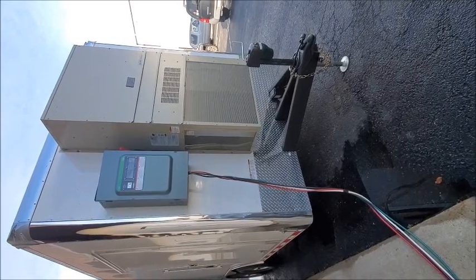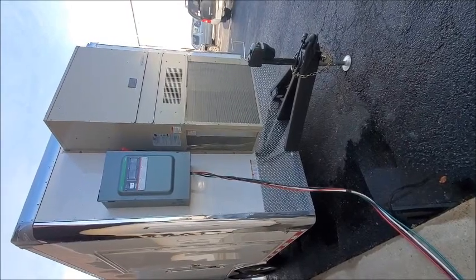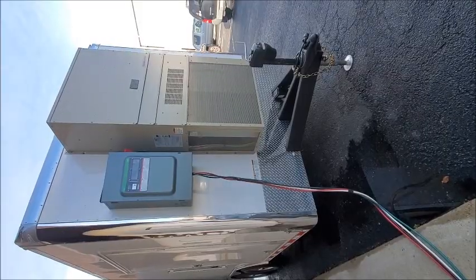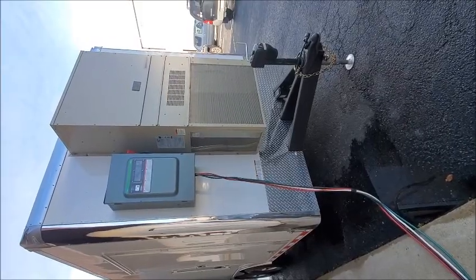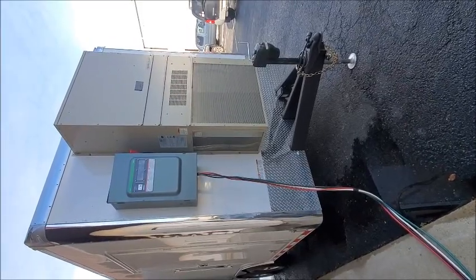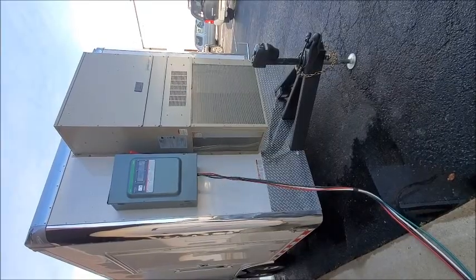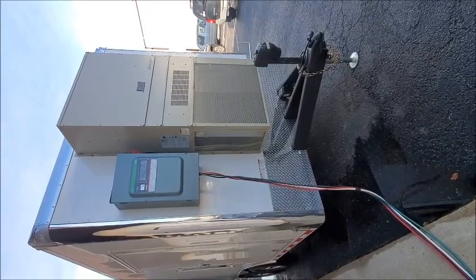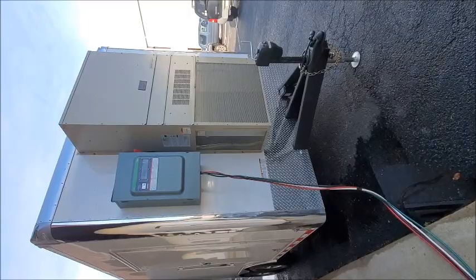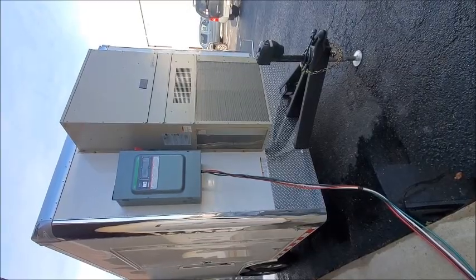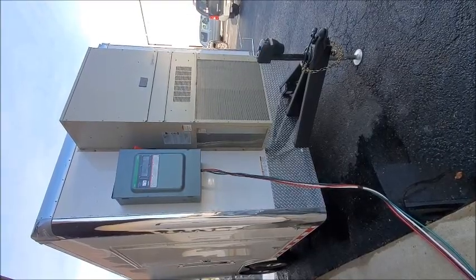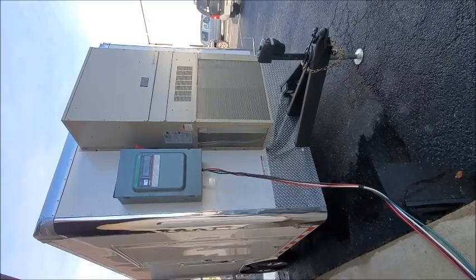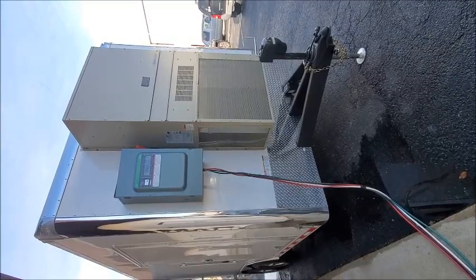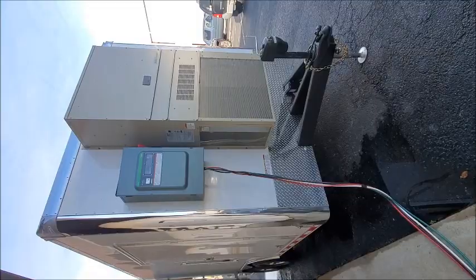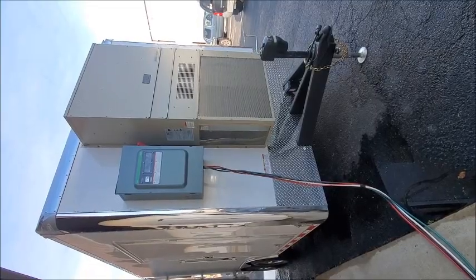This video segment is an overview of features pertaining to the climate control system in the Air Systems International Breathing Air Supply Trailer, BASS-2025. The trailer's primary heating and cooling source is a 2.5-ton, 460-volt, 3-phase, wall-mounted heat pump.